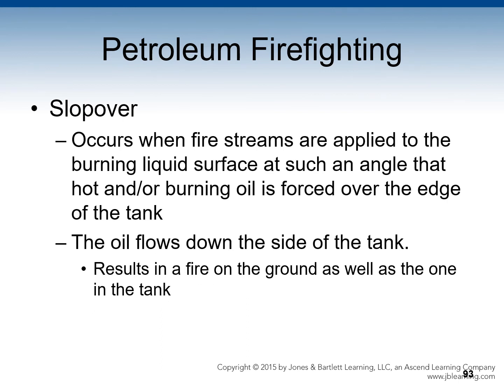Slop over occurs when fire streams are applied to the burning liquid surface at such an angle that hot and/or burning oil is forced over the edge of the tank. The oil then flows down the side of the tank, resulting in a fire on the ground as well as one in the tank.